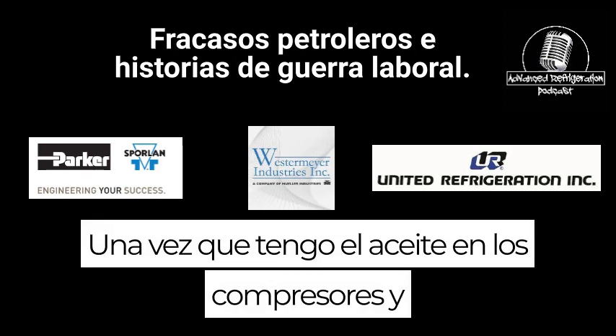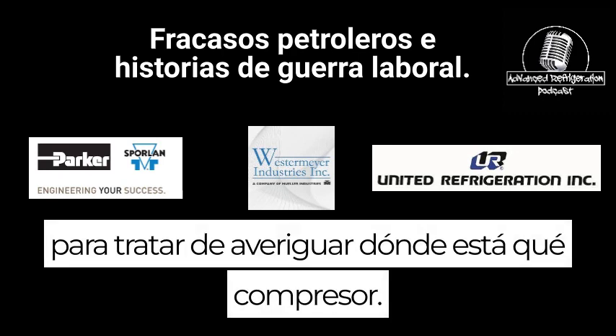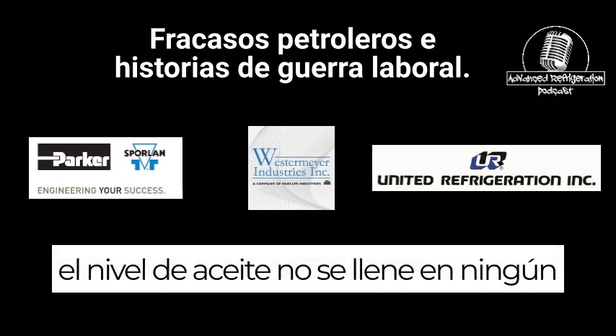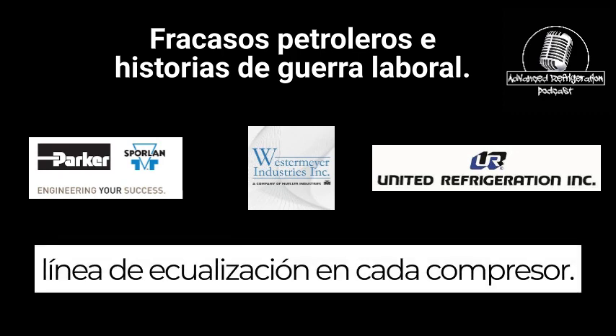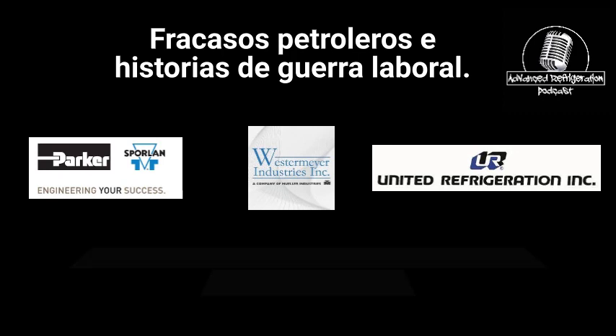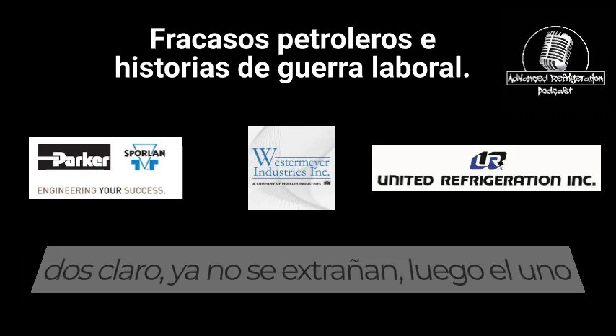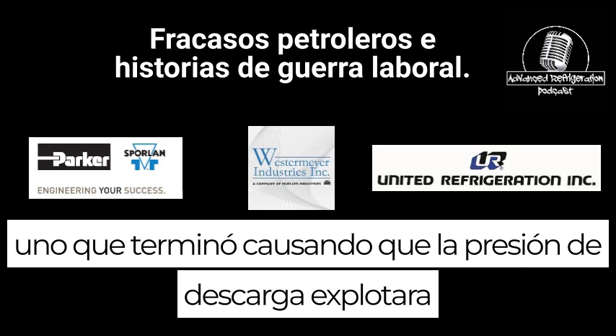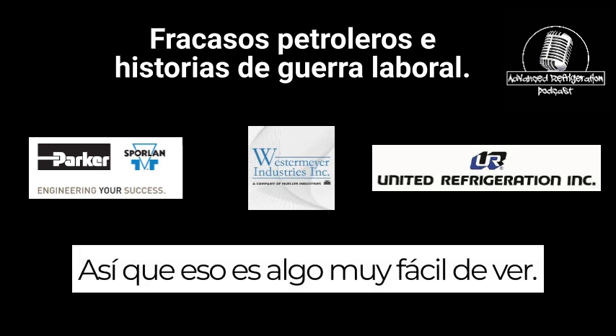Once I get the oil in the compressors and start running them again, I use the misting to figure out which compressor is the culprit, the one causing the discharge pressure to blow into the crankcase, which is keeping the oil level from filling up on any of the compressors. I'm looking for the misting. There's usually a shutoff valve for each equalization line on every compressor. If you see misting in all three, which you will, because that discharge gas is blowing into the crankcase of all the compressors, shut off one equalization line. If the other two clear up and aren't misty anymore, then the one you just shut off is the one that caused the discharge pressure to blow into all the rest of the compressors. So that's a very easy thing to look for. You're basically just looking for misting.